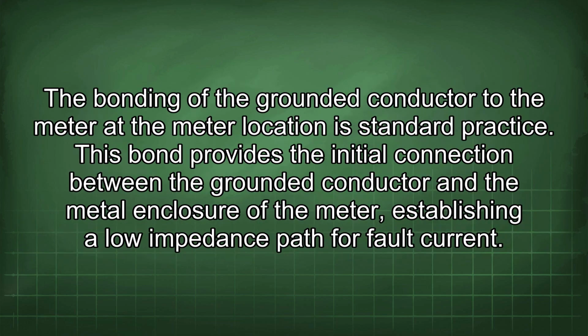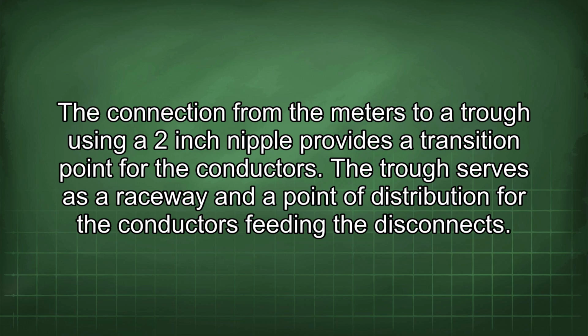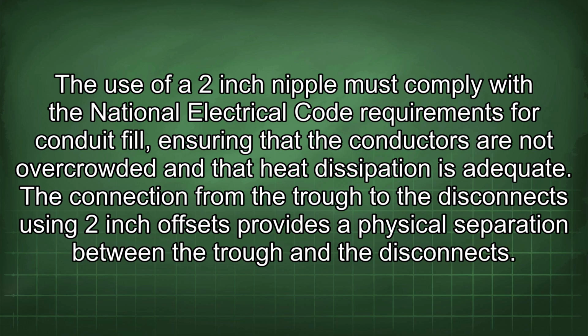The bonding of the grounded conductor to the meter at the meter location is standard practice. This bond provides the initial connection between the grounded conductor and the metal enclosure of the meter, establishing a low impedance path for fault current. The connection from the meters to a trough using a 2-inch nipple provides a transition point for the conductors. The trough serves as a raceway and a point of distribution for the conductors feeding the disconnects. The use of a 2-inch nipple must comply with the National Electrical Code requirements for conduit fill, ensuring that the conductors are not overcrowded and that heat dissipation is adequate.